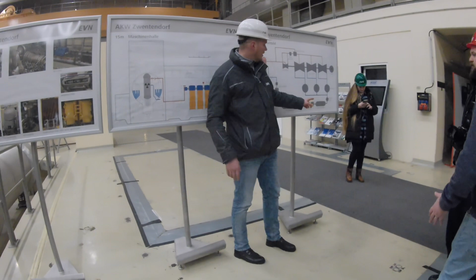The high pressure turbine brings 40% of the overall power of the turbine set. After the preheater, the steam goes on to 3 lower pressure turbines, working from 10 bars down to 0.06 bars. In the end we have 0.06 bars at approximately 30 to 35 degrees, and at this temperature and pressure we still have steam. Therefore we need the condensers to bring the steam back to water, to condense it, and after that the water is brought back to the reactor. Then you have some preheaters, filters, and the pump which brings the water back into the reactor. This is the whole cycle in total.